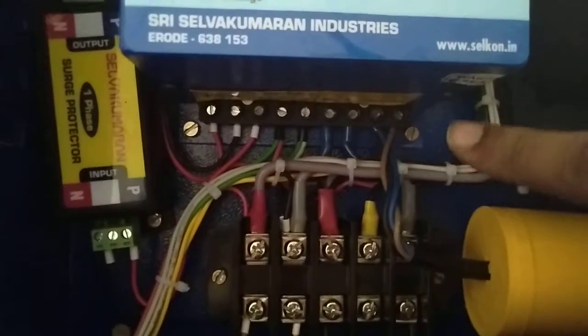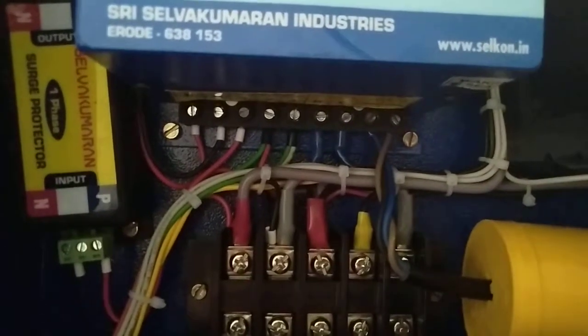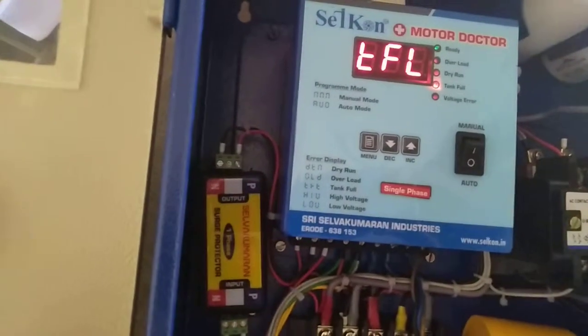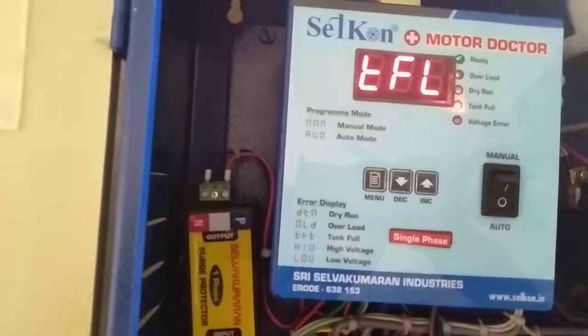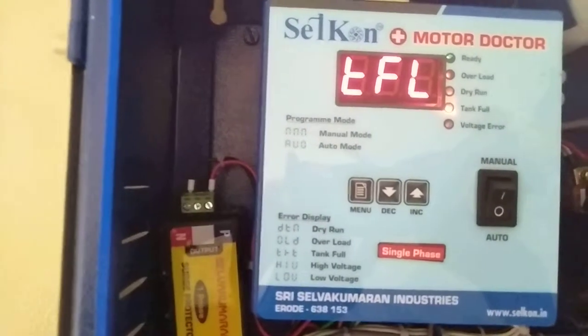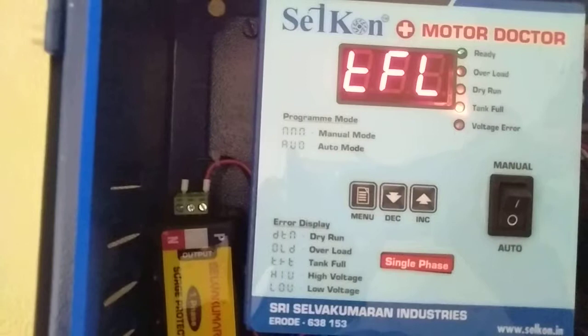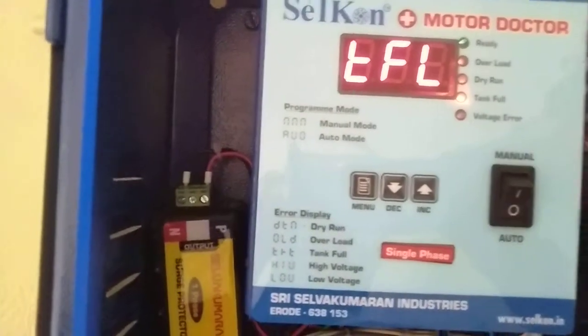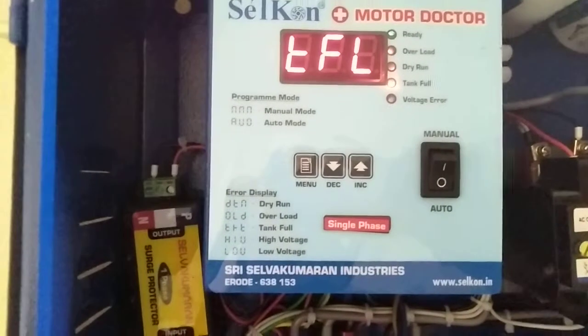So now we see there are water tank wires. There are 2 provisions here. Here the wires are connected. So now we can see the water tank controller. That is a float model. Now the float is at the bottom. That means the tank is empty. Once the water is pouring, the float comes up slowly. Once it reaches the point, the controller automatically shows the error message tFL, that is tank full. Once the tank is full, after the delay time, the controller will switch off the motor automatically. Okay. So now we can see the controller error message and the float position.